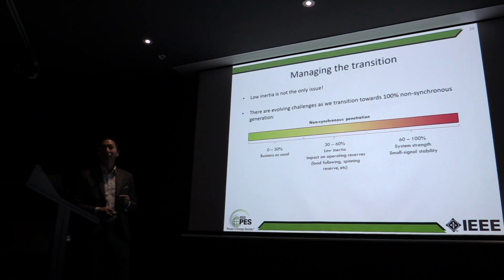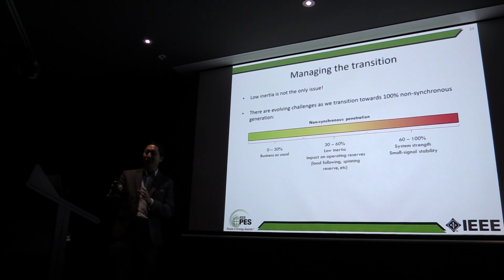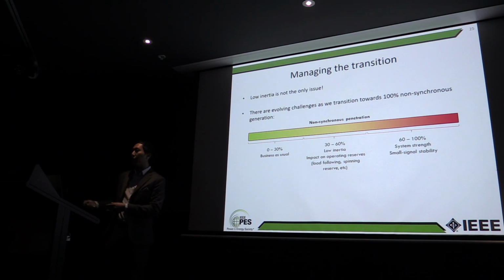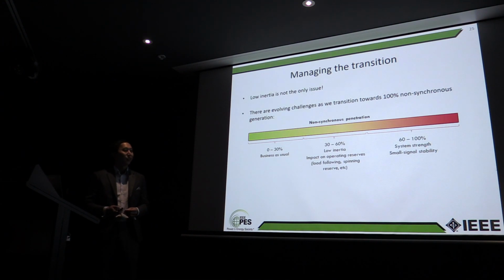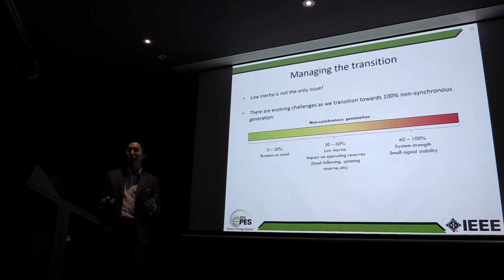The other issue is small signal stability issues, and this is something that we're starting to see a bit more of in the eastern states. This is basically controllers of wind and solar farms fighting each other. This is what's happening over east: there's a wind farm and a solar farm located nearby, and they're acting against each other. AEMO has had to constrain off some of the solar farm during certain times of the day because of the adverse interactions between these machines. We used to have that in the small signal problems in the synchronous machine days, but a lot of those issues got resolved. So presumably we'll come up with methods to quantify and resolve those issues as well going forward.